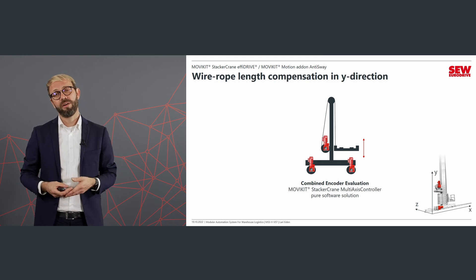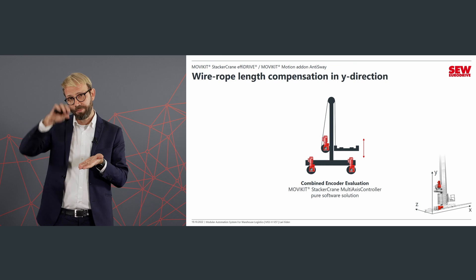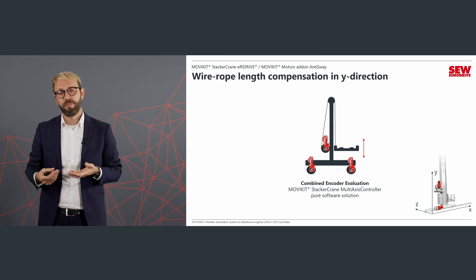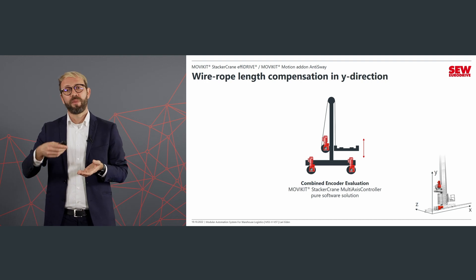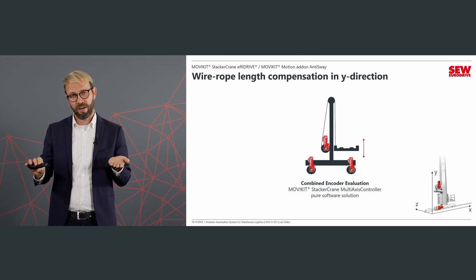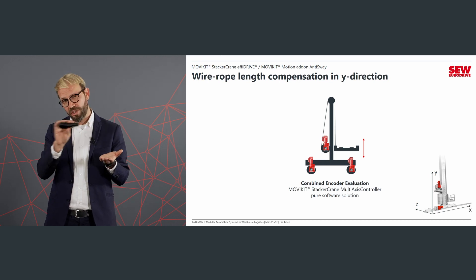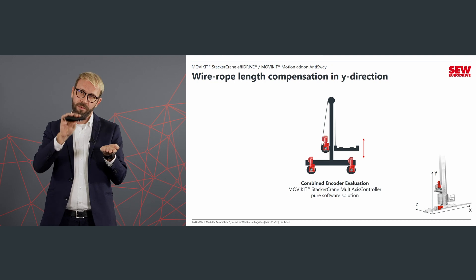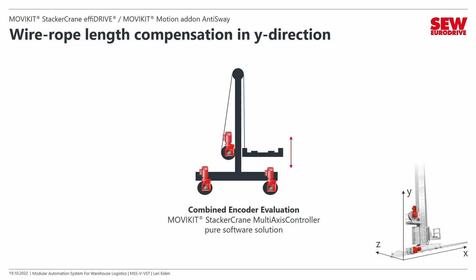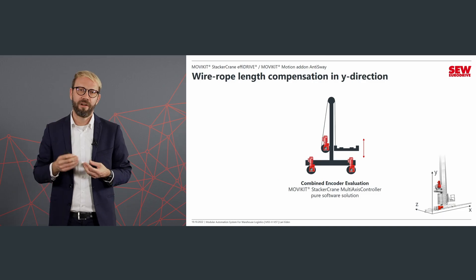The last direction to discuss is the Y direction — the lifting axis. This vibration appears when a load is placed onto or removed from the load handling device and transferred into the shelf. Because the load point is changing, we get wire rope elongation and the load handling device starts to oscillate. For this, we have a function in the MOVIKIT StackerCrane MultiAxisController called combined encoder evaluation. In this case, we use both the motor encoder and an external encoder, combining them to achieve a high-resolution encoder signal with direct machine connection.